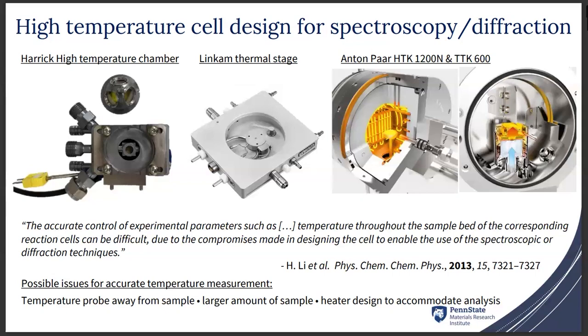So one of the main things that happen in the drift of temperature comes from the fact that the temperature probe is often away from the sample, because we cannot do the spectroscopy and have the temperature probe where we are doing the spectroscopy. The amount of sample we are using is larger, so often in the tens of milligrams up to hundreds of milligrams, which leads to differences of temperature at different places of your sample, and just the design of the heater in order to accommodate the spectroscopy or diffraction.